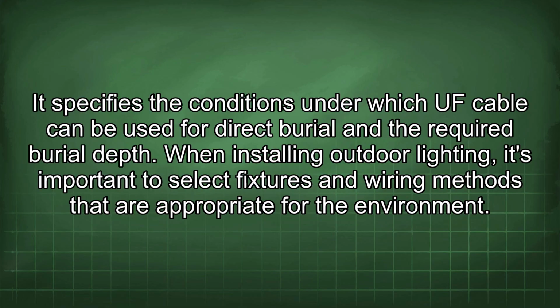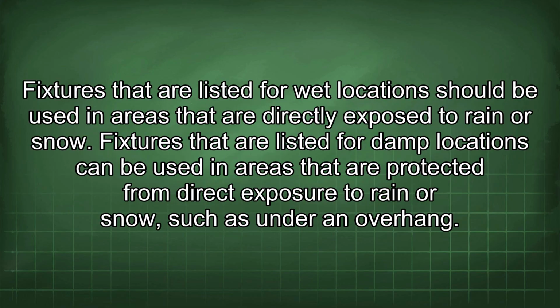When installing outdoor lighting, it's important to select fixtures and wiring methods that are appropriate for the environment. Fixtures that are listed for wet locations should be used in areas that are directly exposed to rain or snow. Fixtures that are listed for damp locations can be used in areas that are protected from direct exposure to rain or snow, such as under an overhang.